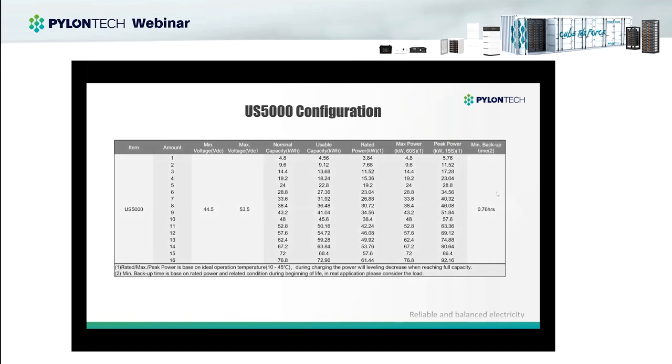Here is a configuration list for the US5000. Different quantities of modules give you different nominal and usable capacities. Usable capacity equals nominal capacity multiplied by DoD — 95% — giving you the usable capacity. Rated power means the discharge current ability: the rated power for one module is 3.84kW, max power at 60 seconds is 4.8kW, and at 15 seconds is 5.76kW. When designing a system, you need to consider the average load, the peak load, and the required backup hours, then choose the inverter power capacity and battery bank capacity accordingly.